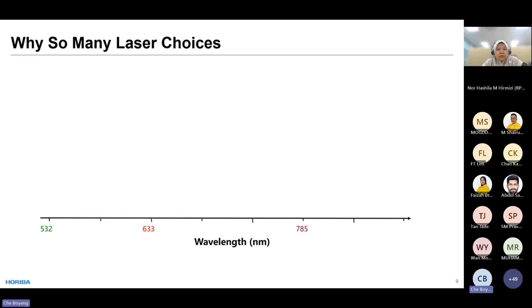Since all different lasers are supposed to give you the same spectrum, why do we still provide so many laser choices? There are several reasons. One of the main reasons, which you will sometimes see on your real sample, is that we try to avoid fluorescence when we do the Raman test. Here is the same result I showed you just now. If we test the same sample using three different lasers and use wavelength as the x-axis, we're supposed to get the same pattern, just appearing at different values. That is in principle.